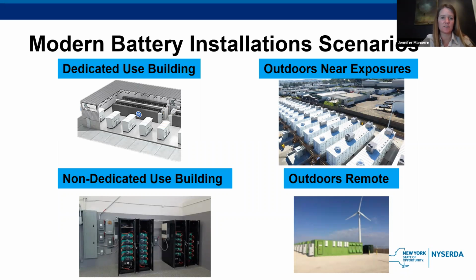So the different sections vary based on whether or not it's a dedicated use building, which means it essentially is only storing batteries and it's not used for anything else, or a non-dedicated use building, which is, as it sounds, anything that's not a dedicated use building. So maybe there's office space in there and you happen to have a battery energy storage system somewhere in the building. Non-dedicated use buildings are obviously going to have slightly more stringent requirements than a dedicated use building because there are human life safety concerns associated with them.